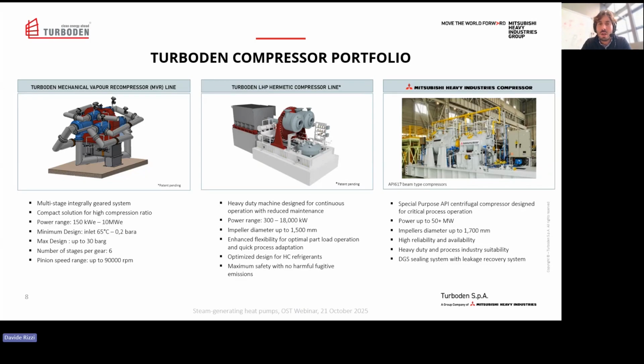In the middle, we developed a patented integrally geared compressor, called the Turboden LHP hermetic compressor. In this case, we propose for our heat pumps an integral gear compressor, multi-stage, designed to work with hydrocarbon but also other compatible fluids. This system has particular features tailored for heat pump applications working in closed loops. On the left side, last but not least, is the mechanical vapor compressor, so steam compressor.